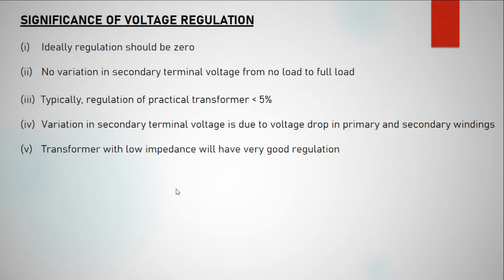Significance of voltage regulation: ideally, regulation should be zero. An ideal transformer would have regulation of 0, but an ideal transformer does not exist in the world, so there will always be some regulation in a transformer. But the regulation of a practical transformer should be less than 5%, and then it is called a very good transformer. So what is regulation? It is the variation in secondary terminal voltage from no load to full load. If there is no significant change in the secondary terminal voltage, then its regulation will be very low.